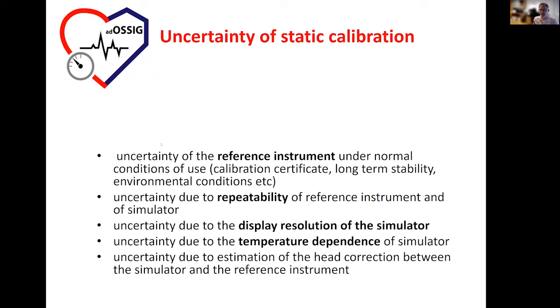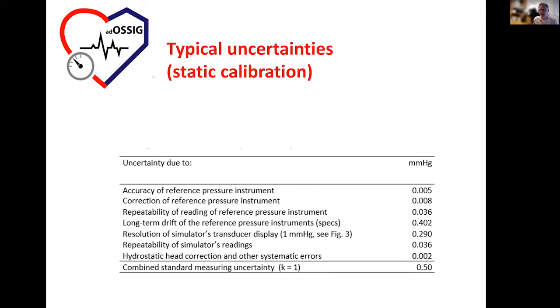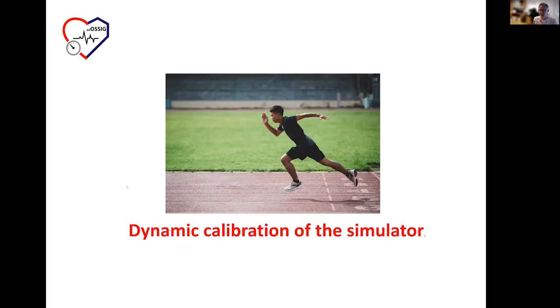And this is really nothing new. Here are some typical uncertainties. These are the numbers. This is something which every pressure lab is capable of doing. So basically what we did in the static calibration part, we calibrated statically the pressure transducer of the simulator. But the interesting part was, of course, the dynamic calibration.